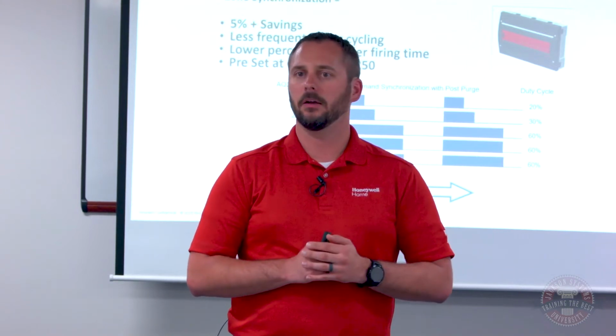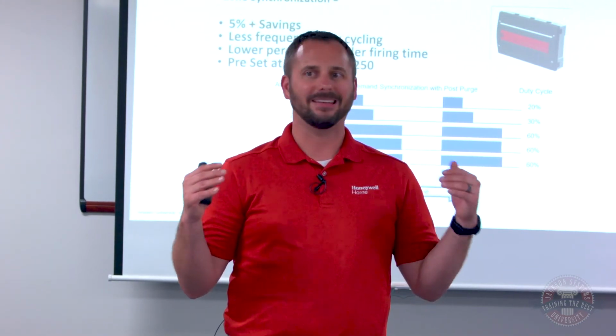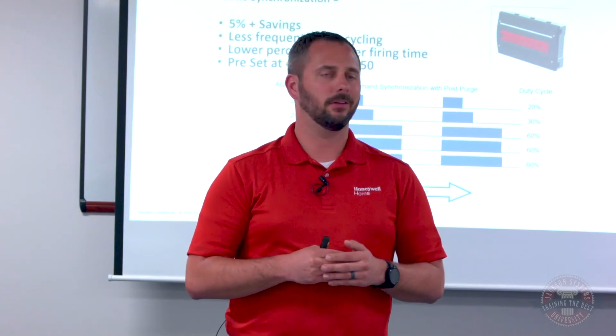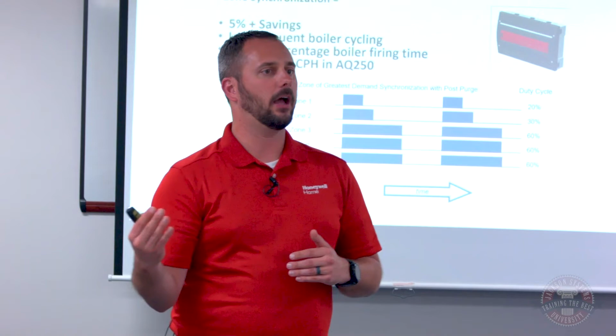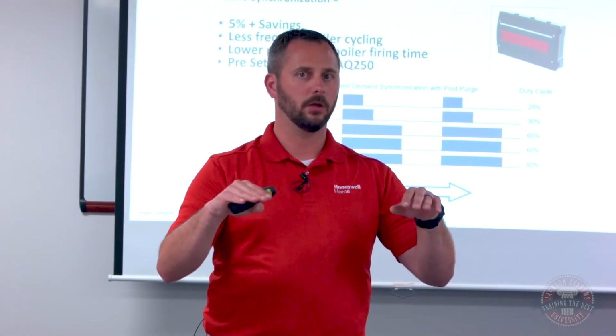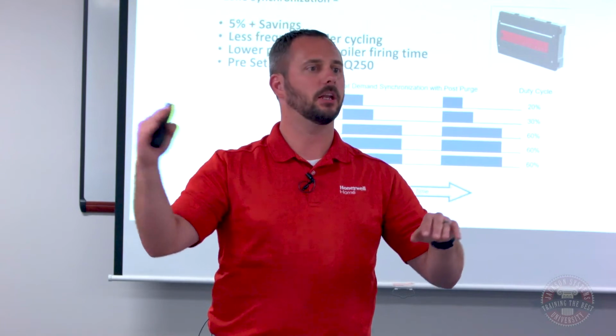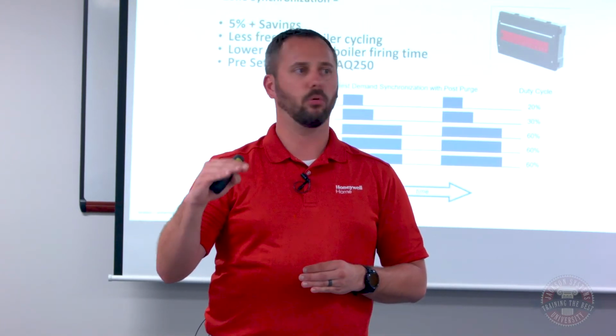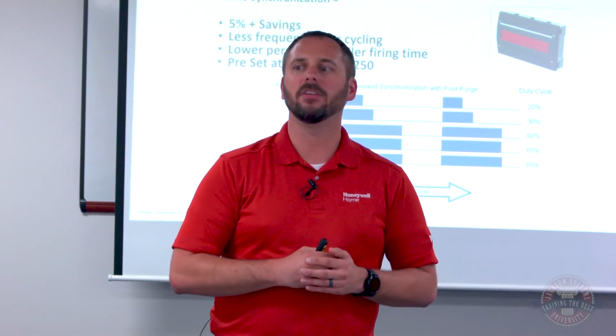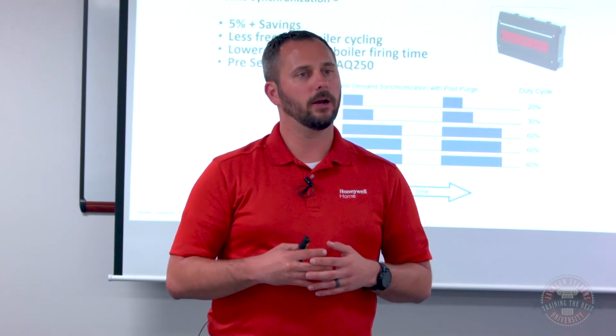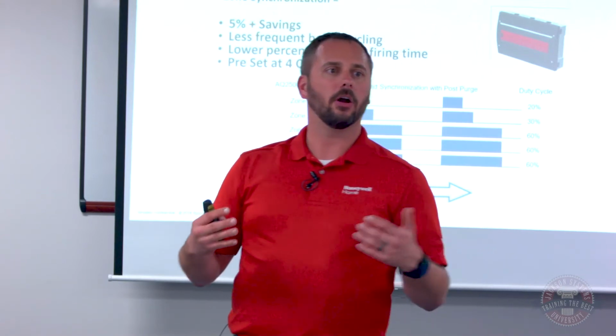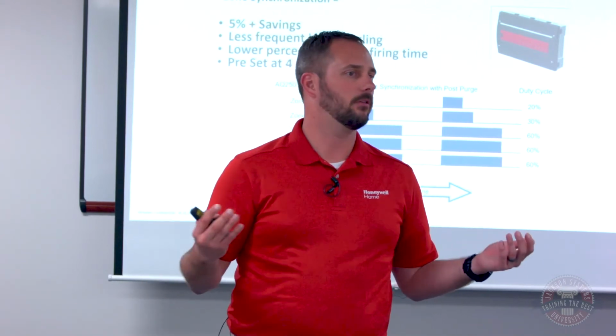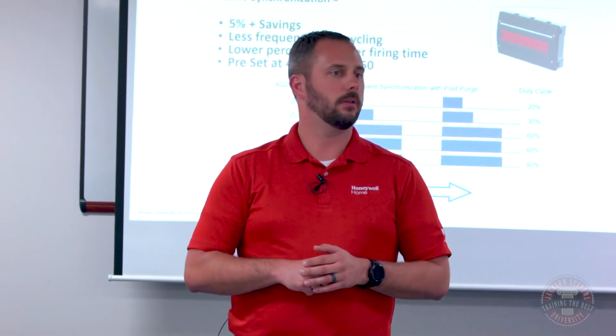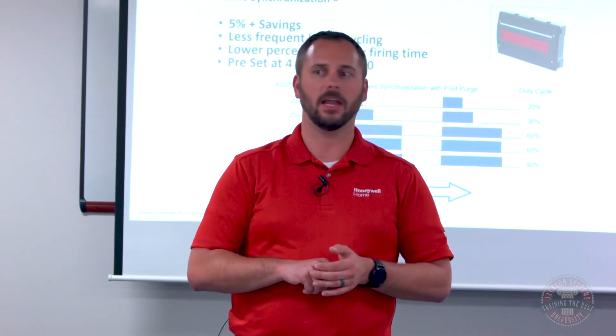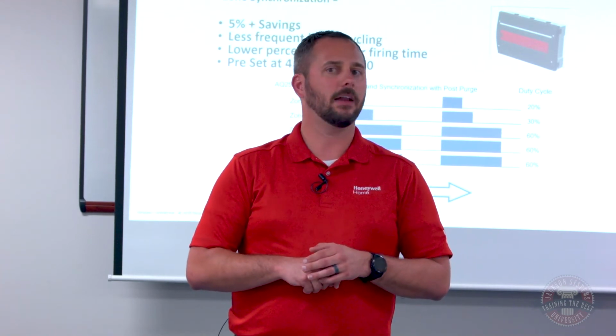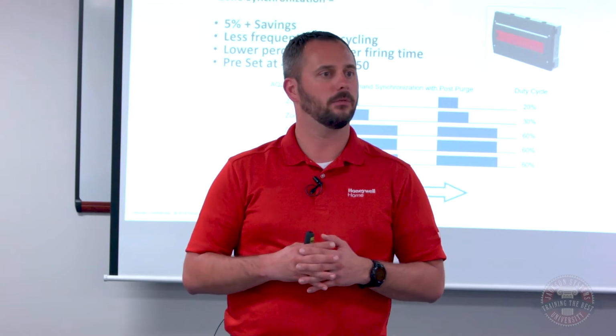You lose some of the efficiency, but what it does is you're able to put the entire system in, and you're essentially setting it for cycles per hour. So it will put a delay on the last call for heat. So let's say you got a call for heat on all your thermostats, and then it shuts off, and you get another one that calls two minutes later. It's going to delay the boiler firing for, could be 5 to 10 minutes, depending on how it's set up. So in a radiant heating system, if you shut the water off for, say, 5 to 10 minutes, it's not going to do anything. There's going to be no perception by the end user. The one exception to that is hydronic fan coils, because you're blowing air again. But with any kind of hot water radiant, if you shut it off for a short period of time, they're not going to feel it.